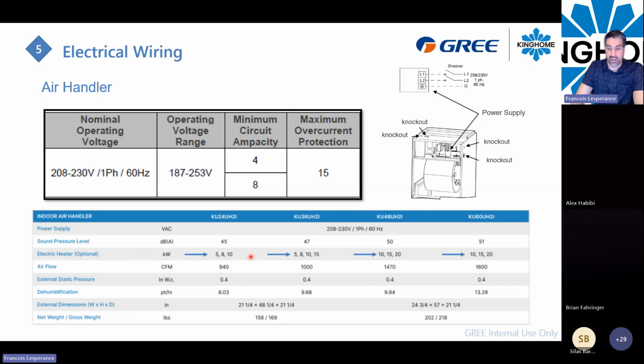If you install electric heater as an optional, make sure you will install the right gauges for the power of your electric heater, and so make sure you work with your electrician at that point to make a good connection. So I've just said at the beginning, there's some knockout here on the top, but I will recommend you to not use it, because at a certain point, if you need to remove this top panel here for your installation and servicing the air handler, well, if you pass your wiring through that knockout, you will have some difficulty to move that panel around, and that will create a little mess. So always use a knockout from the side of the unit. It's better for you, and it's easier to work with.